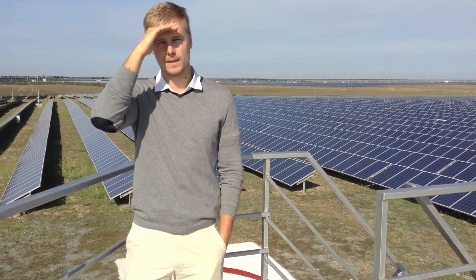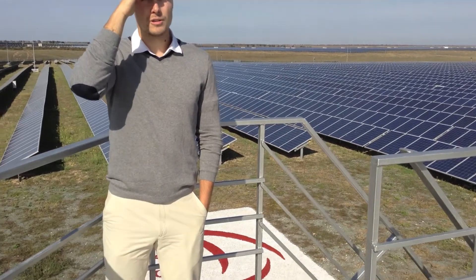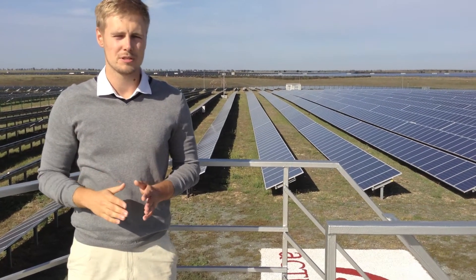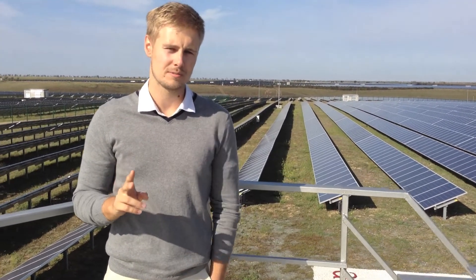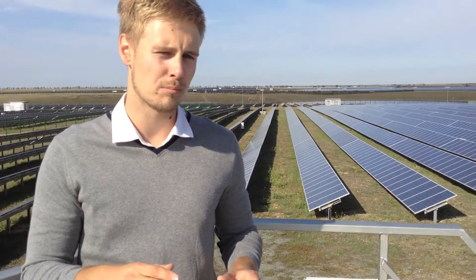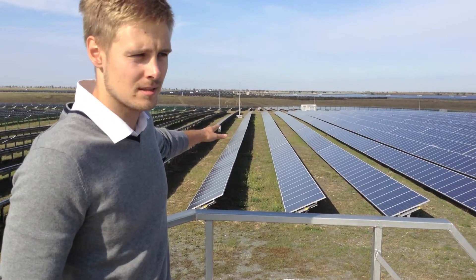On this power station we have more than 400,000 panels. We also have more than 100 inverter stations — each inverter station has a capacity of half a megawatt. Inside each inverter station we have two inverters with a capacity of 250 kilowatts and one transformer that steps voltage up to 10 kilovolts. We also have plenty of GCBs that transfer electricity from solar modules to the inverter station.